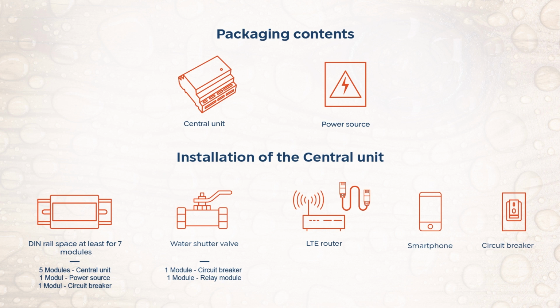To install the unit in the electrical switchboard, you will need space on the DIN rail for at least 7 modules: 5 modules for the central unit, 1 for the power source, and 1 module for a circuit breaker, which is not included. If there is a water shutoff valve in the installation, an additional relay module is required and a separate circuit breaker solely for the valve is strongly recommended. All you need is a mobile phone to connect to the activation interface to control the system.